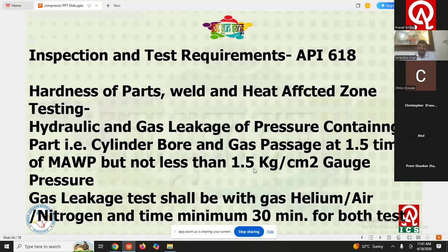There is one condition which I have not reflected here: pressure gauge selection is also one crucial requirement. Whenever we are selecting the pressure gauge, the range shall be 1.5 to 4 times the testing pressure. So if my testing pressure is 60 kg, my gauge range shall be 1.5 to 4 times of this, which means the gauge will be 90 kg to 240 kg. So gauge selection is also one crucial requirement.